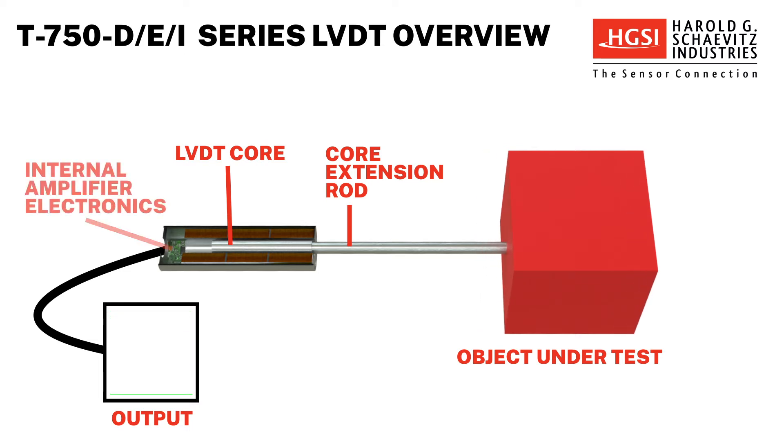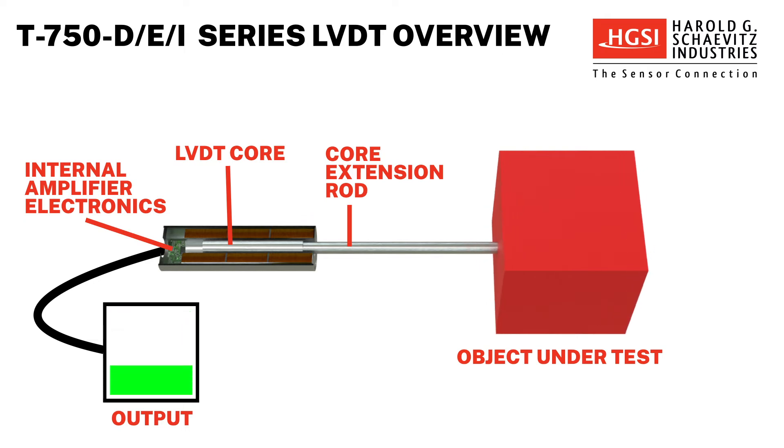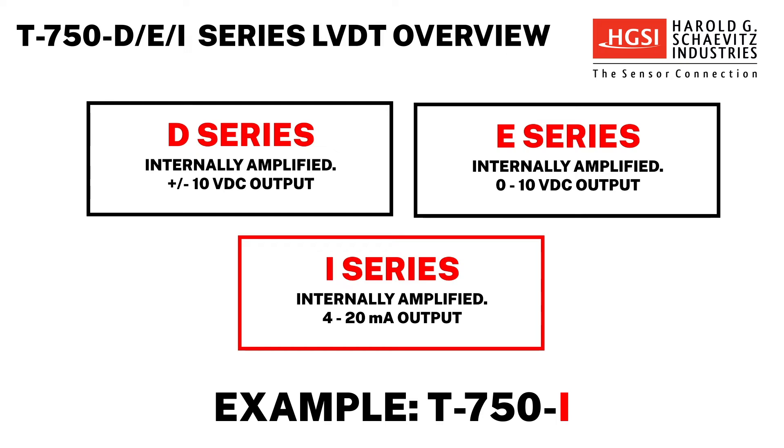These rugged DC LVDTs are built with internal amplifier electronics, so no external signal conditioner is required. The D Series is internally amplified with a plus or minus 10 volts DC output. The I Series is internally amplified with a 4 to 20 milliamps output.